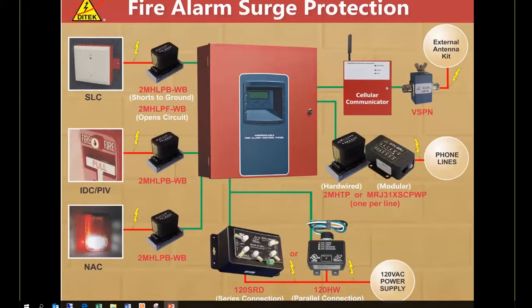On the communication side, for your phone lines, typically you're going to have 2 phone lines coming into your fire panel. We have 2 methods here. We have a modular device, which is the MRJ31X SCPWP. That is for 1 line. Typically with 2 lines, you're going to need 2 of those devices for that phone line protection. Or you can do a hardwired screw-down terminal-based device, which is a DTK-2MHTP WB, meaning with base, that would protect both pairs of wire with a single point ground. The MRJ31X you would need to make sure that each surge protector has its own ground run. So the hardwired device, you only have to ground once, versus 2 MRJ31Xs, 1 for each component.